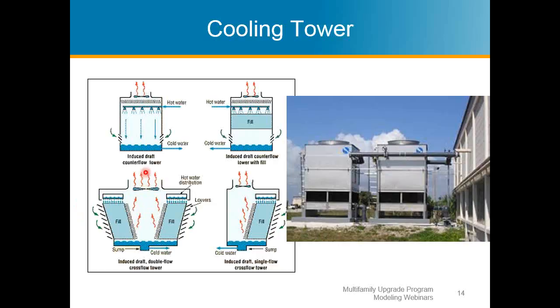If you ever go out in the morning when it's cool and see big plumes of steam coming out of the roof of somebody's building, you don't have to call the fire department. It's not on fire. It's basically just steam, the cooling tower doing its job and working. It's going to cool down that water. The water rains down on the fill and gets collected in the sump. Now, obviously, through evaporation you're getting less water coming down, so there's a fill line in the bottom. I believe you can see it in this picture, it's this guy right here that I'm circling. That's going to replenish the water you need, because you're losing water through evaporation. So now you have cold water down here, and it gets piped back to the chiller to start the whole process again.